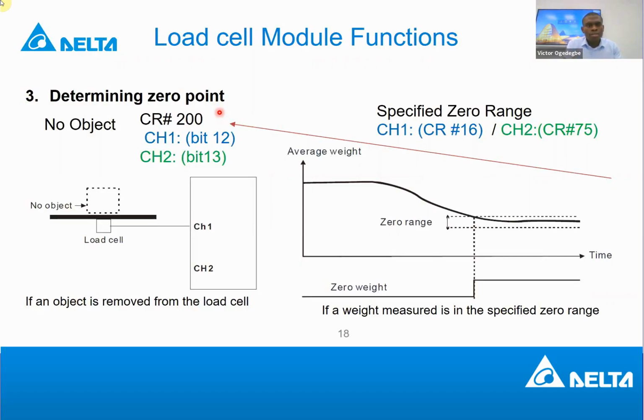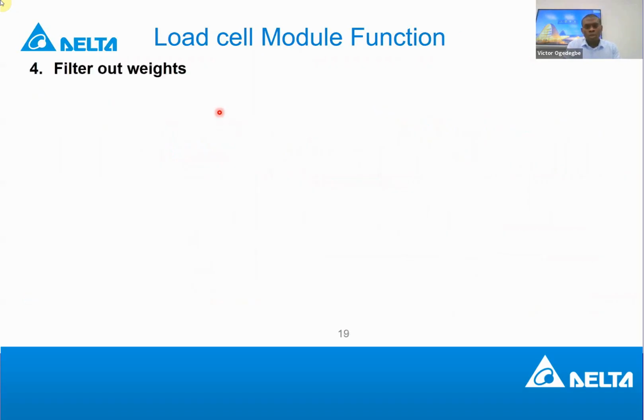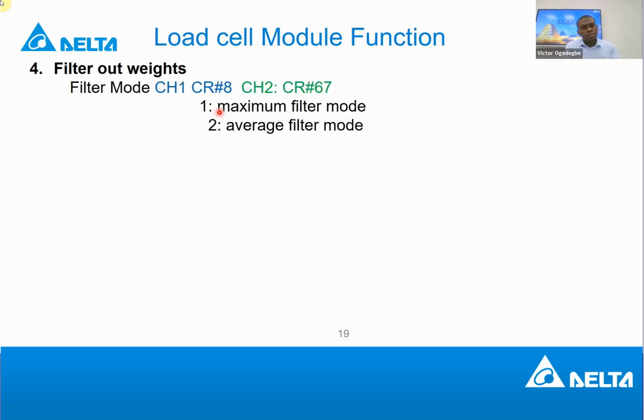The fourth function that we offer in this module is filtering weights. Sometimes when you are measuring weights, the weight you are measuring is being distorted. Like one of our colleagues on the call asked, can you connect load cells together? Then you connect it to the module. It's like your average of what is being measured. So that is being done to make sure that what you are measuring is balanced. But in some cases, you could have some interference, some noise, and the measurement is not stable. Then you can use this function to filter.